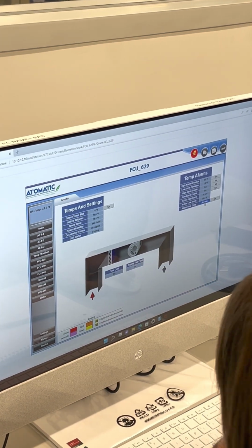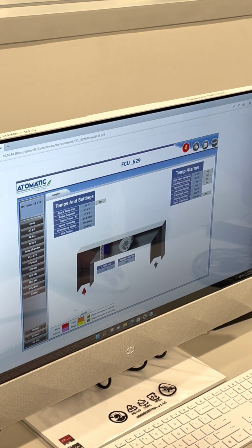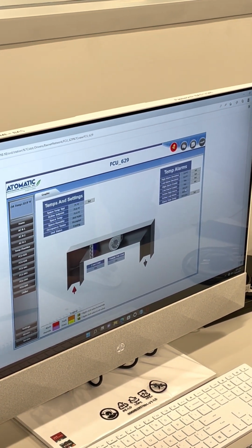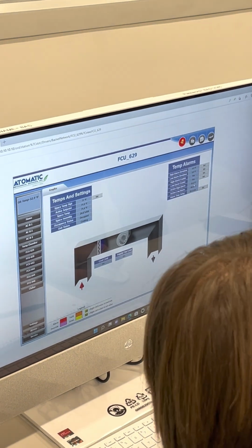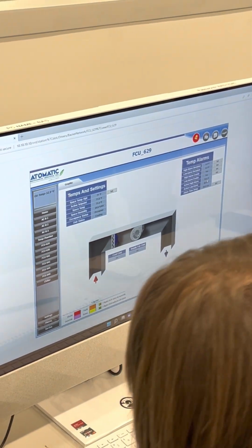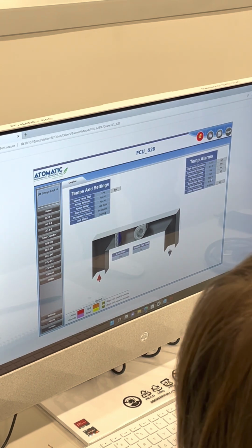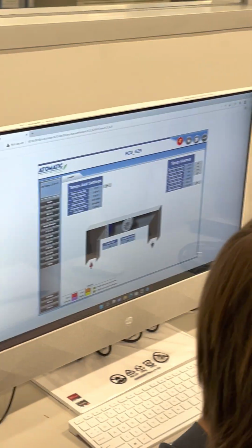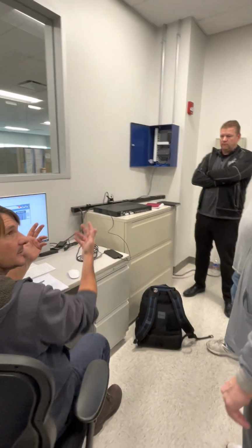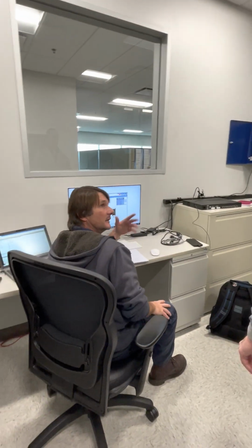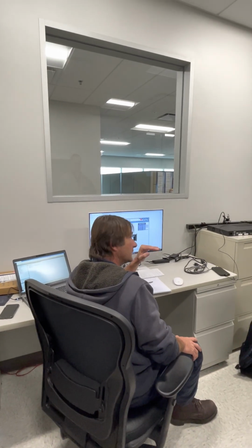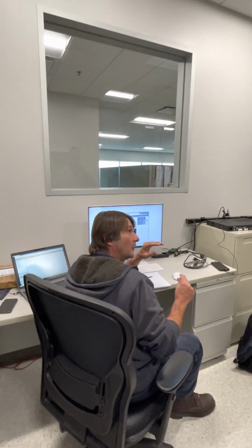What does that mean exactly? What that means is if my space temperature gets to 76.1 degrees, it's going to wait 30 minutes before it generates an alarm out. You don't want it instantaneous on temp alarms. There needs to be a delay in there. You can get any type of fluke, doors opening, someone walking by with something hot or warm that's going to cause that. So I want it to be above that 5 degree dead band for 30 minutes before I generate an alarm.